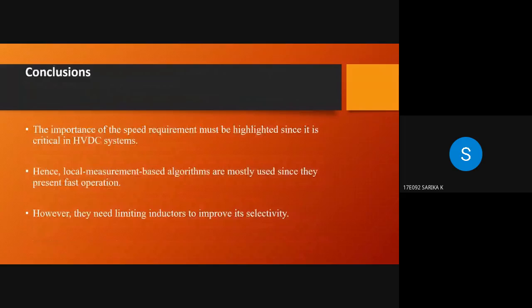And it is now time to conclude. The importance of the speed requirement must be highlighted since it is critical in HVDC systems. Hence, local measurement based algorithms are mostly used since they present fast operation. However, they need limiting inductors to improve their selectivity.